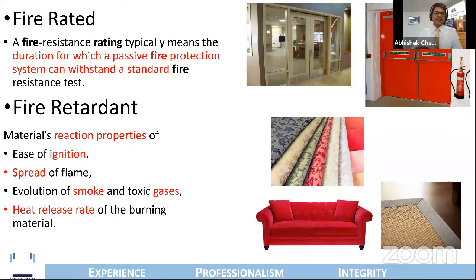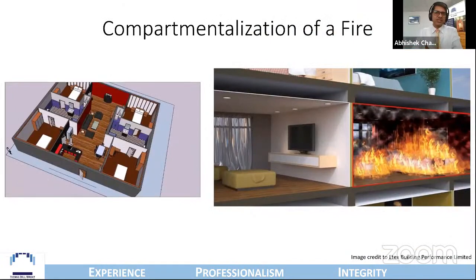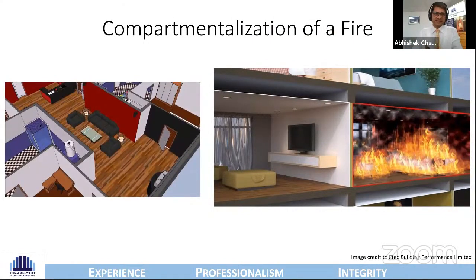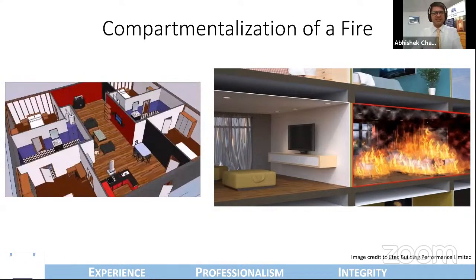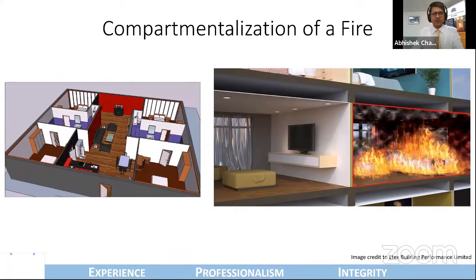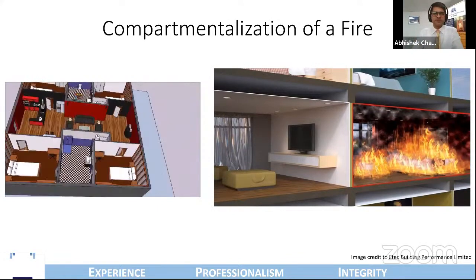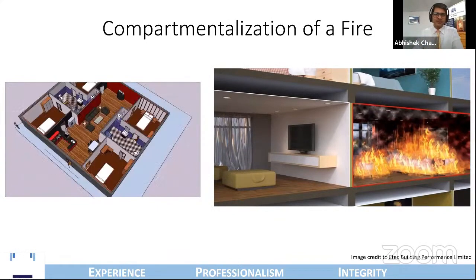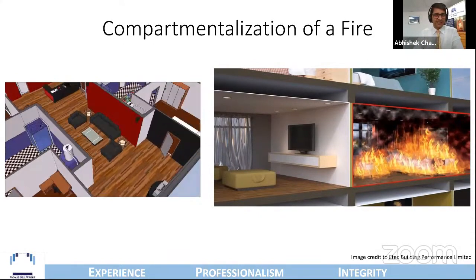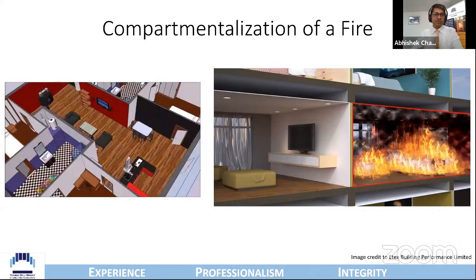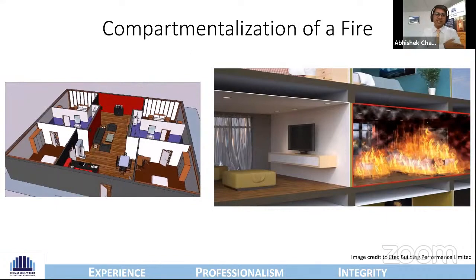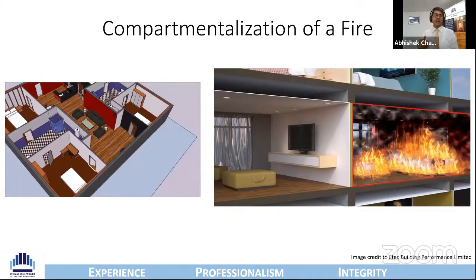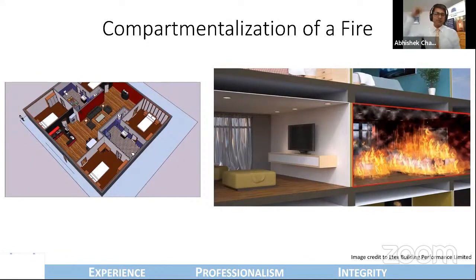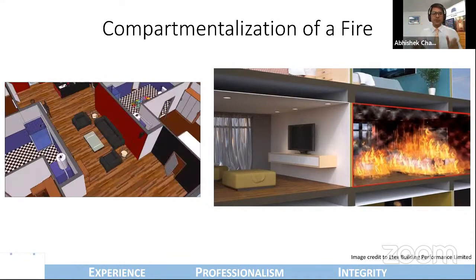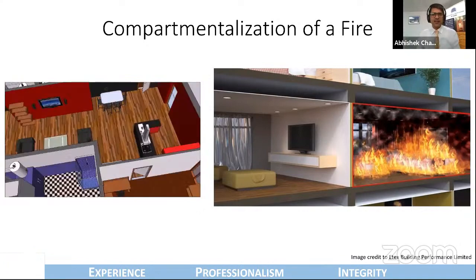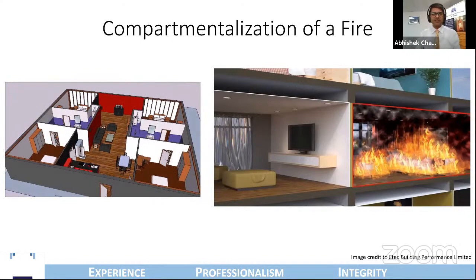Now let us understand how compartmentalization is designed and implemented correctly. If you see the image on your screens, there is a fully developed fire in one section of the building. Despite this fire, which is releasing smoke and hot gases and is often at a very high temperature, upwards of 800 to 900 degrees Celsius, the other sections of the building, above, adjacent, below, as well as the section above the false ceiling, are contained and protected. This is containment, and delivering it requires a lot of effort.